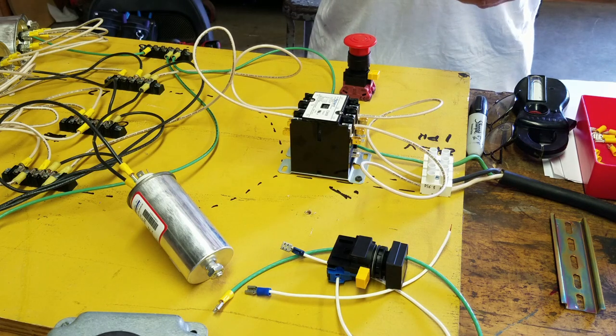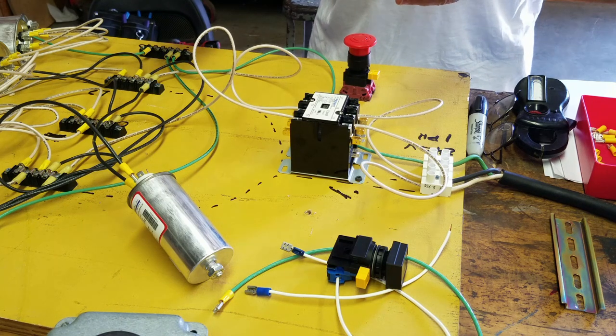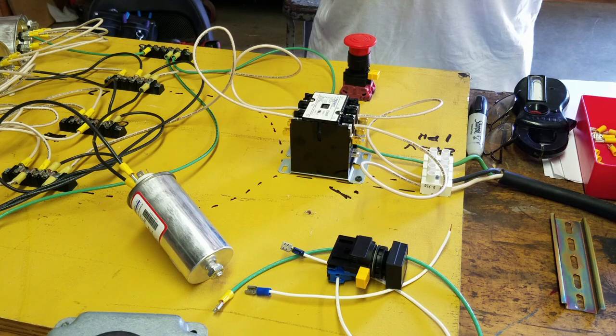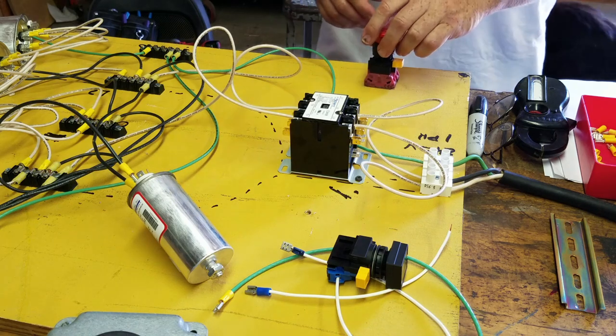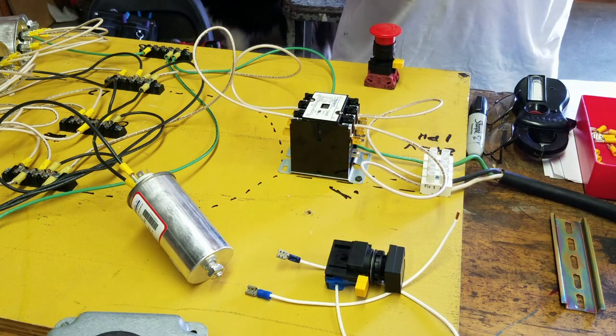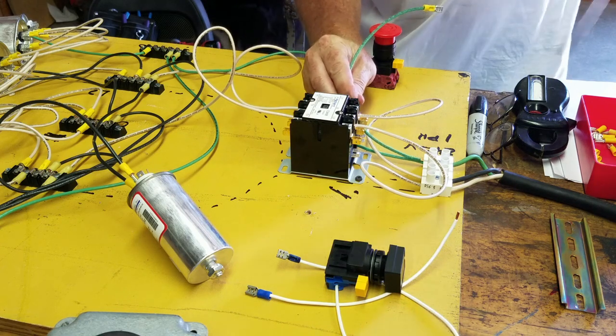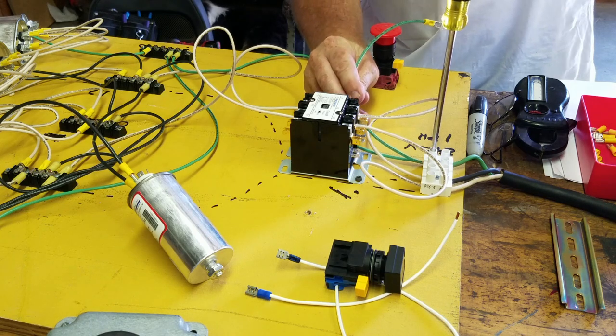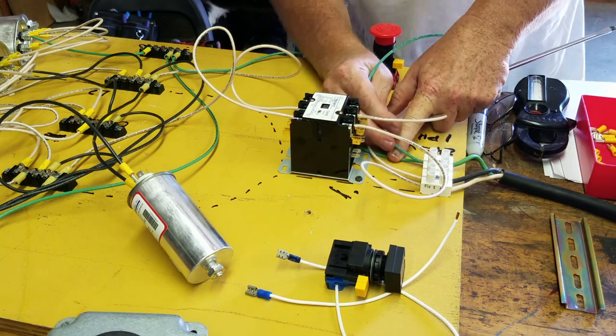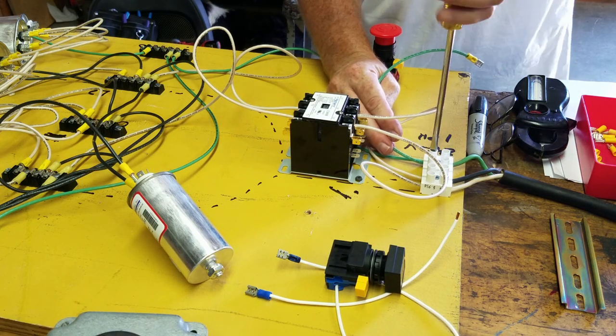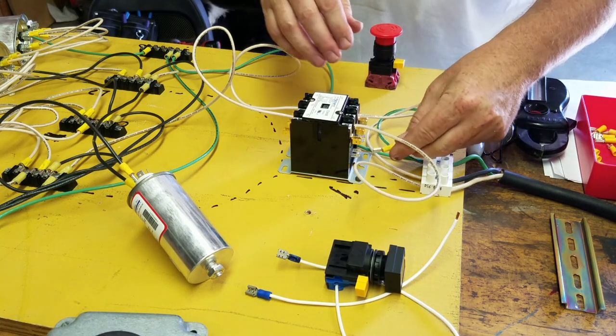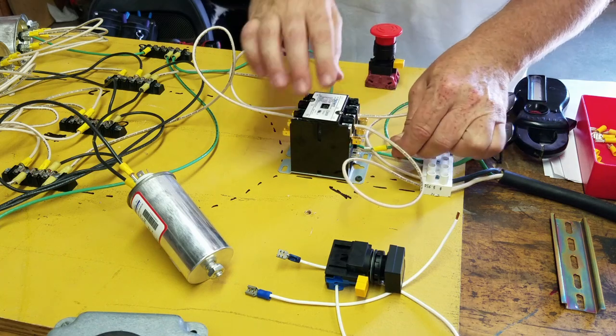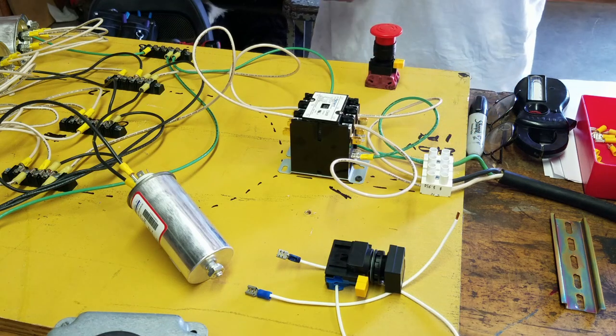The activation of the magnet is what closes the switch and allows everything to go. If you deactivate that magnet, the switch opens up and the rest of the circuit shuts down. So what we need is, first off, because this coil is 110, we're going to cheat a little. And because this is technically just a 220 circuit, not a 110-220, we're going to borrow a leg off of the ground. And over here on this other side is where the coils hook up. We're going to hook this to one side of the coil. Just trust me when I say it's one side of the coil.